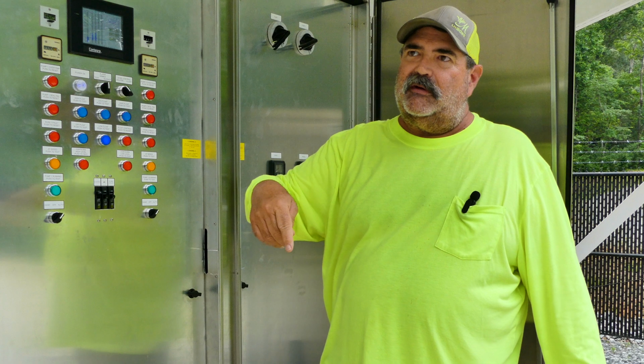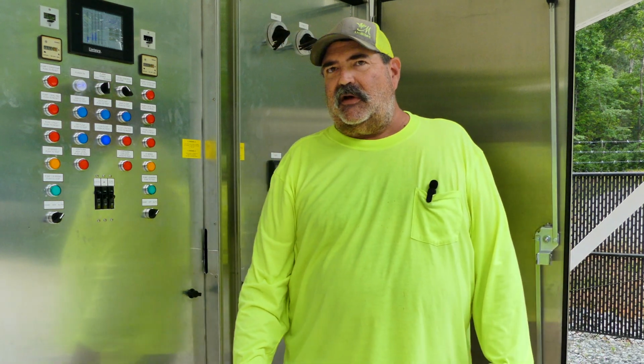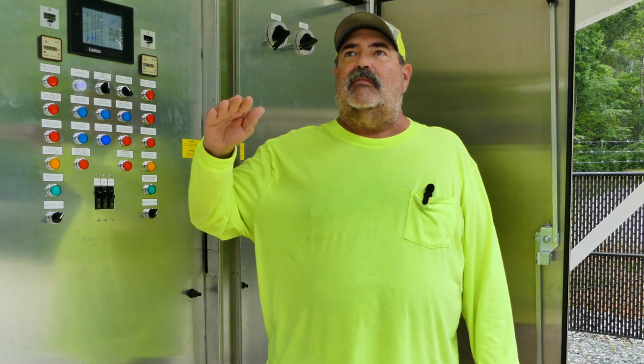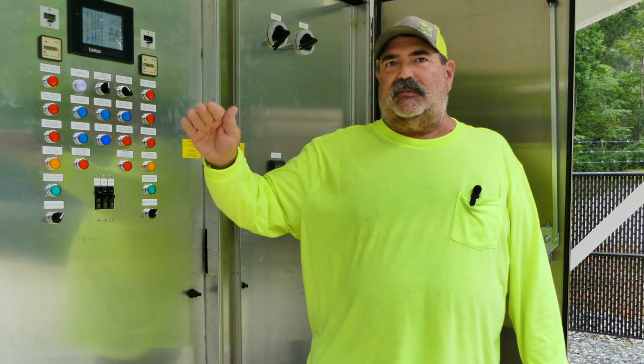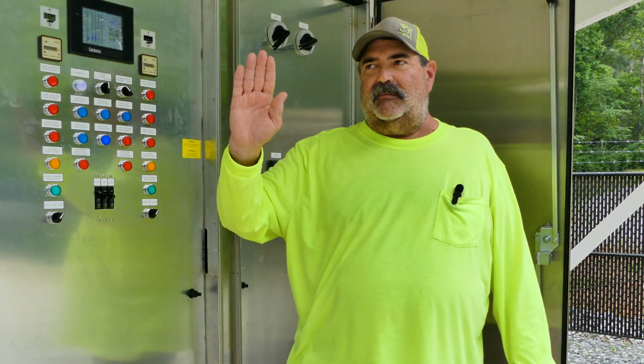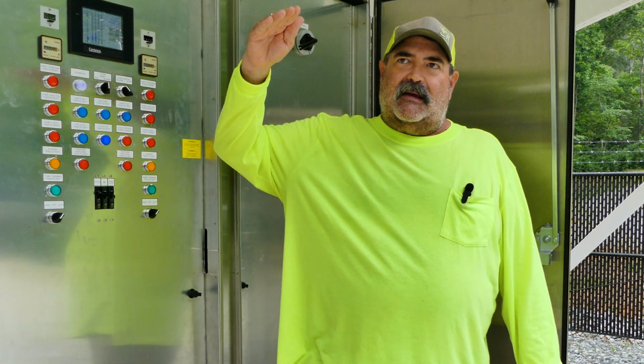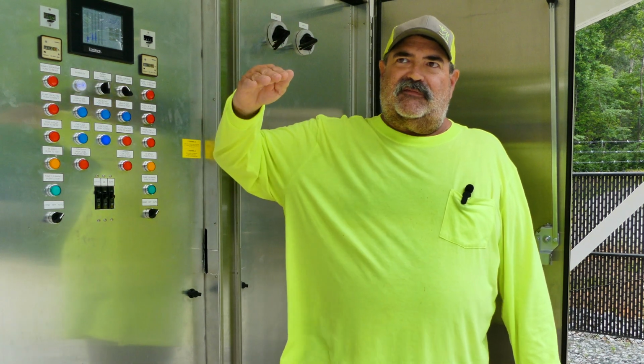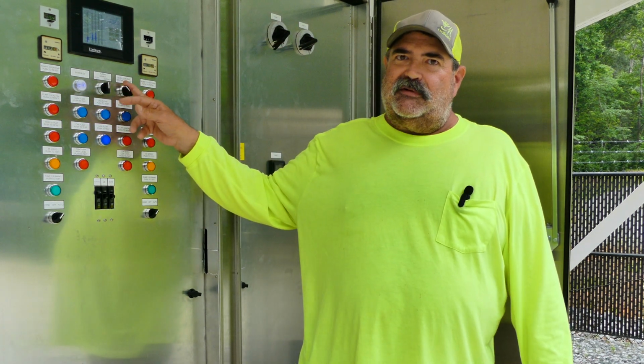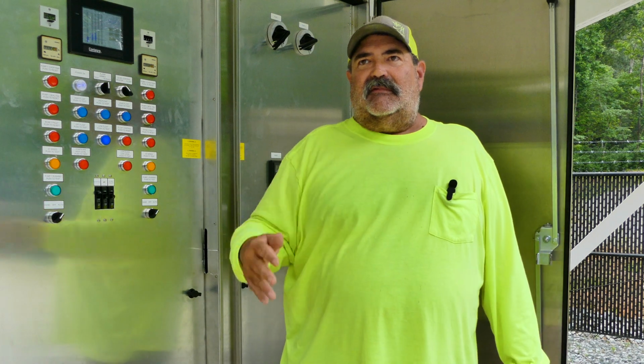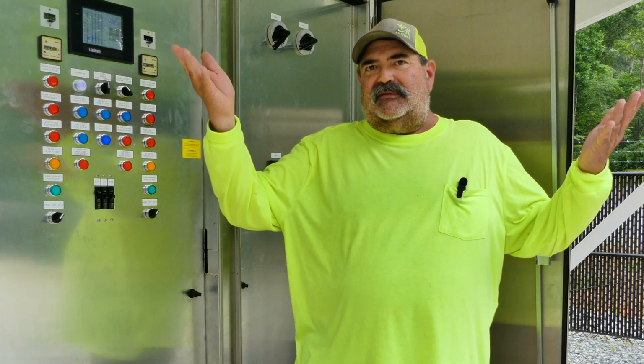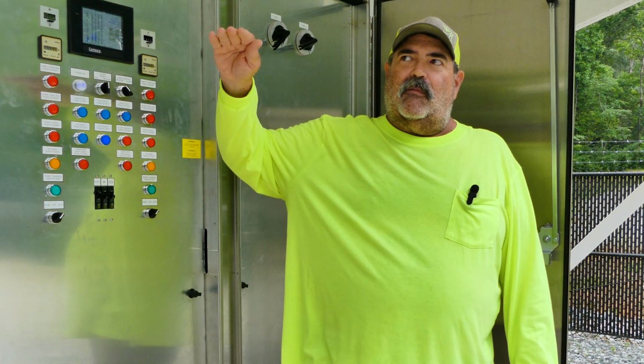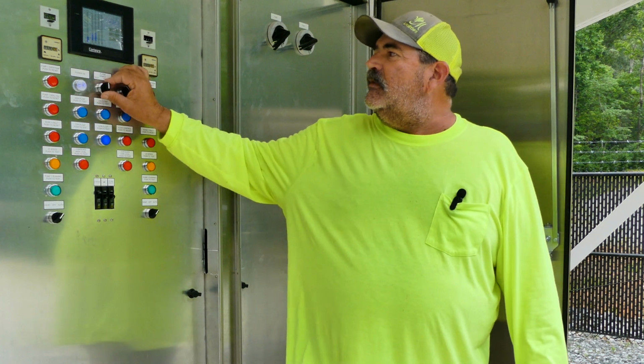There are floats in the wet well. Your lowest float is your cutoff float. Your next float is your lead float that cuts the pump on when the float tips up. Your next float, if that pump can't pump it down, turns on your second pump, which is your lag. If there's a problem and the water keeps rising, it's going to get to the top float, which is a high water float, and that's when you're going to hear this.